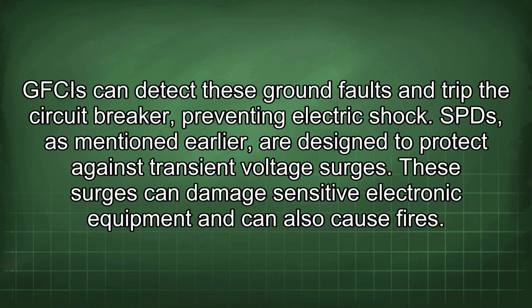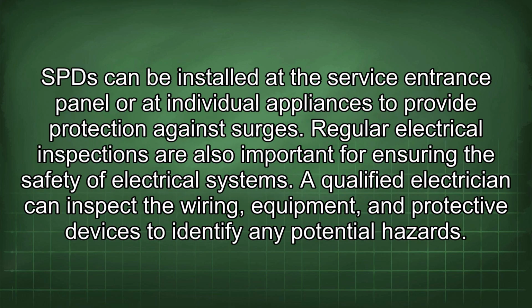SPDs, as mentioned earlier, are designed to protect against transient voltage surges. These surges can damage sensitive electronic equipment and can also cause fires. An SPD can be installed at the service entrance panel or at individual appliances to provide protection against surges.